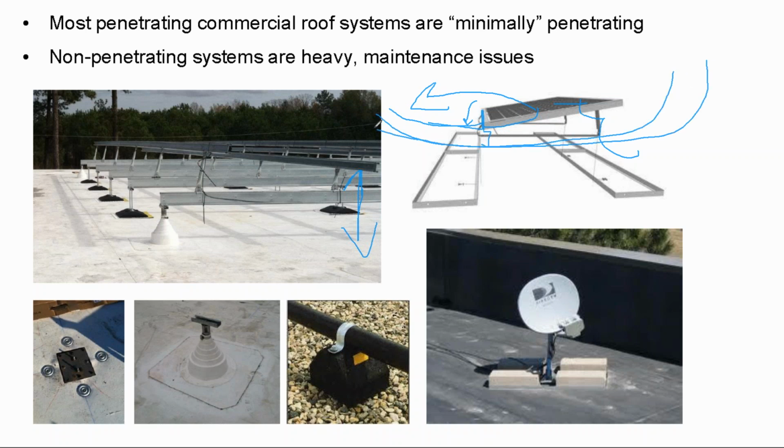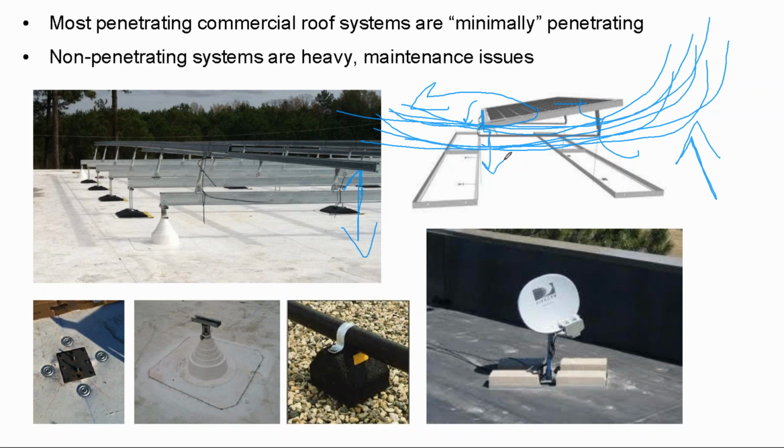Now, when you start getting lots of home run circuits being strung outside of conduit, and keep in mind solar cable is rated to be outside of conduit, so if you're pulling a lot of cable together outside of conduit, that cable is going to sag and touch that roof deck. And in addition to temperature derate implications, there's also the more severe implication of, well, what happens when those conductors get water on them? The water can start climbing up the cable and cause equipment failure.